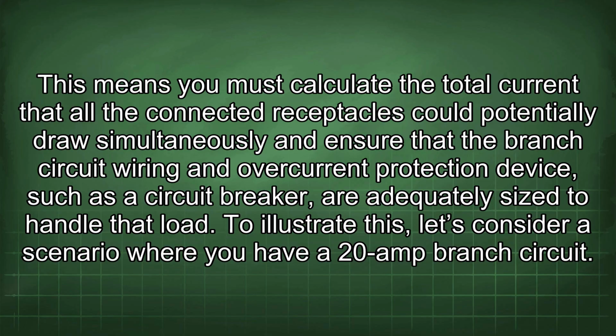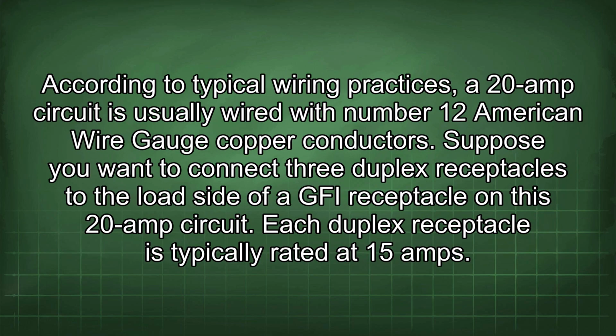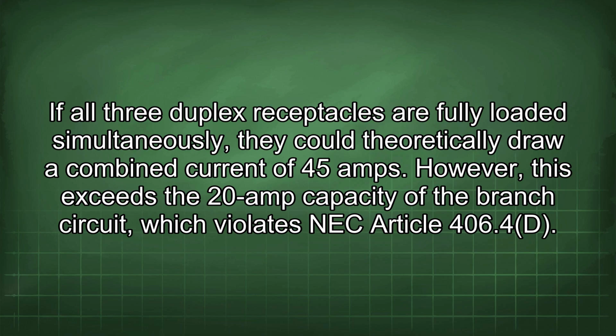To illustrate this, let's consider a scenario where you have a 20 amp branch circuit. According to typical wiring practices, a 20 amp circuit is usually wired with number 12 American wire gauge copper conductors. Suppose you want to connect 3 duplex receptacles to the load side of a GFI receptacle on this 20 amp circuit. Each duplex receptacle is typically rated at 15 amps. If all 3 duplex receptacles are fully loaded simultaneously, they could theoretically draw a combined current of 45 amps. However, this exceeds the 20 amp capacity of the branch circuit, which violates NEC Article 406.4d.